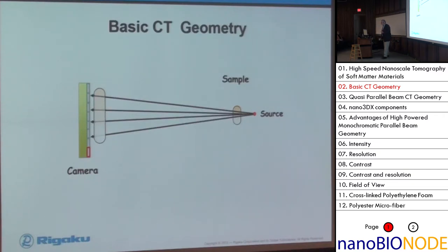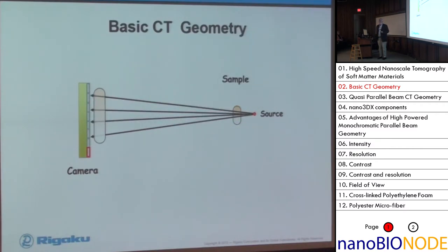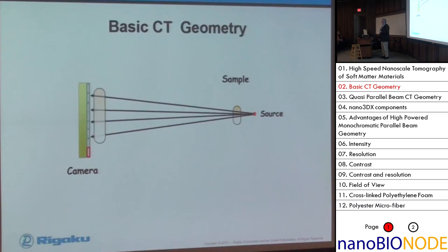This basic CT geometry suffers from a few inherent problems, one of which is the source needs to be very, very small in order to have the resolution. If the source was larger, the resolution would be worse. But because the source is so small, we really can't load it with a lot of x-ray power. If you're familiar with how you generate x-rays, you take an electron beam and shoot it at metal - that metal then will fluoresce x-rays, but it also generates a lot of heat. If you put too much power onto that small spot, you just melt the source.